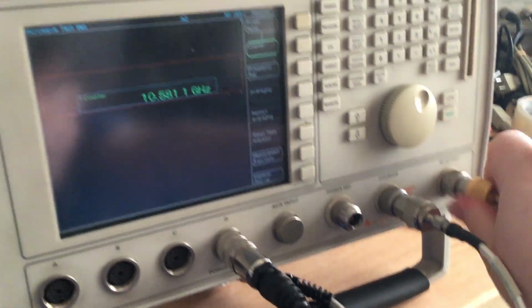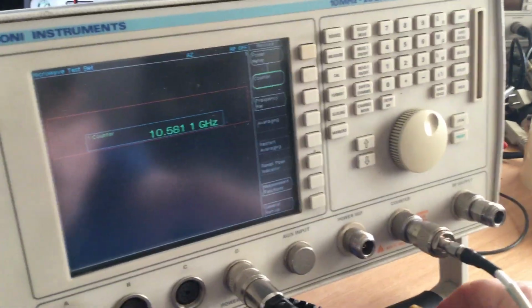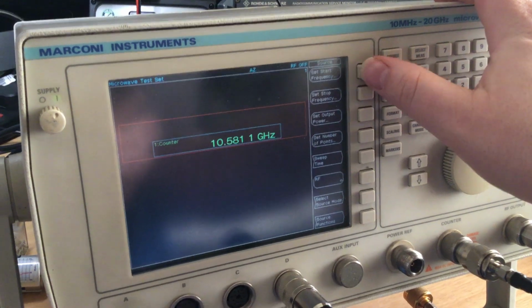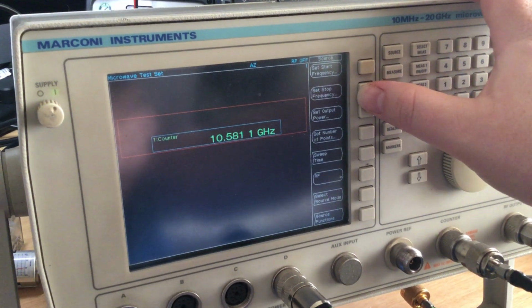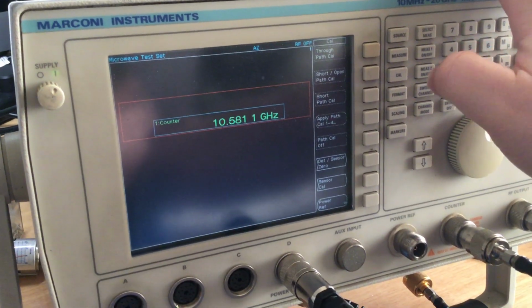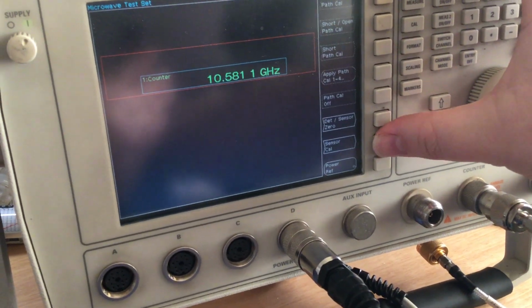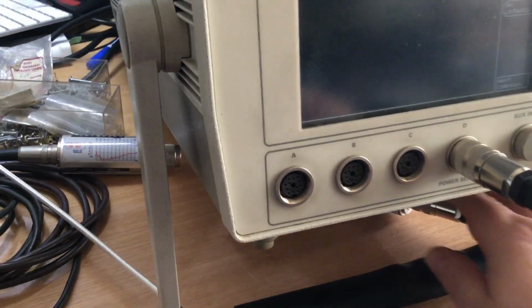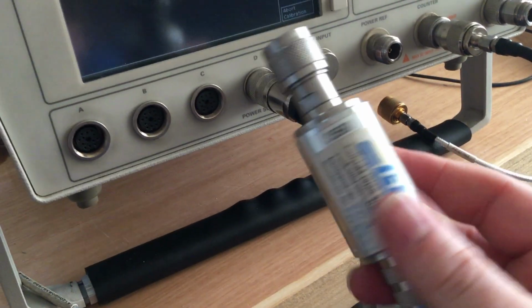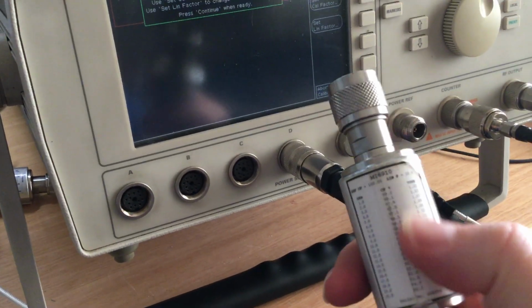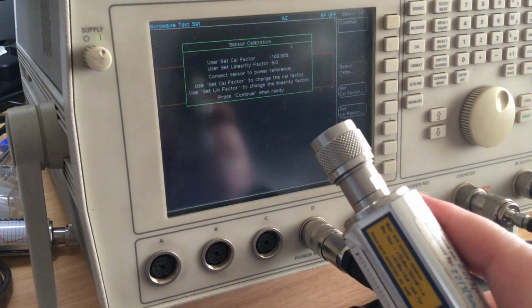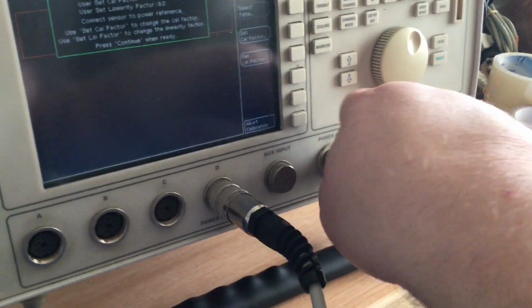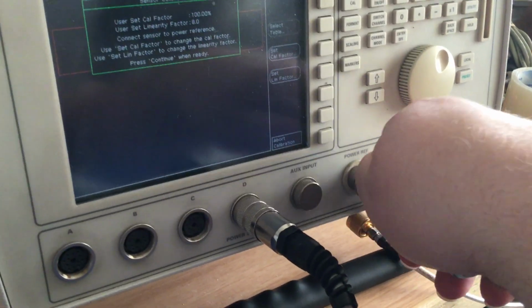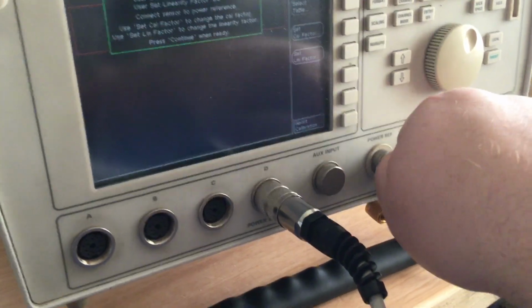So what we need to do now is remove this. We'll just go to source. We will go to yes, we're okay, calibration, and then there is sensor cal. Now this is where we take the power sensor. This power sensor is connected to the D input, and the calibration data that's on this label is entered in to the test set, and the calibration data is all held in this, which I've already manually entered. So we connect the detector first of all to the power reference port, because we need to calibrate the detector first before we do any calibrations of the RF output. So we'll connect that up.